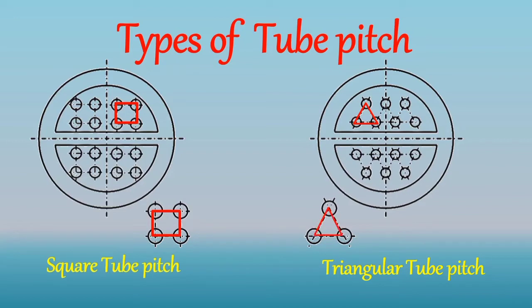With a triangular pitch arrangement, a larger number of tubes can be accommodated in a given shell diameter compared to a square pitch arrangement. In a triangular pitch arrangement, large turbulence is created in the shell side fluid. If the fluids are very clean, a triangular pitch arrangement is used.